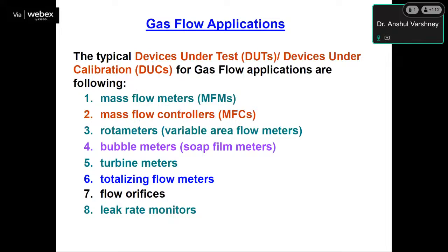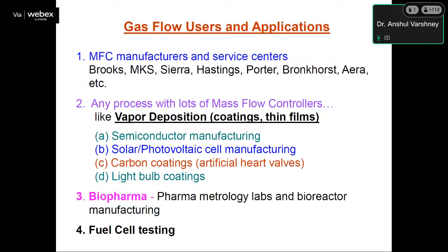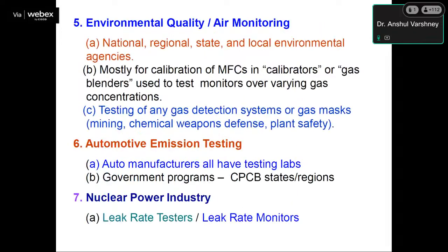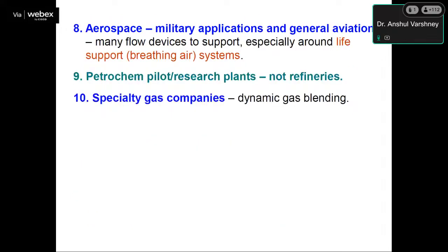So basically, gas flow applications. The typical devices under test for gas flow systems are mass flow meters, mass flow controllers, rotameters, bubble meters, turbine meters, totalized flow meters, flow orifices, and leak rate monitors. We provide service to mass flow meter manufacturers and their service centers like Brooks, MKS, Sierra, Hastings, and so on. Applications include any process with lots of mass flow meters, biopharma industries, fuel cell testing, environment and quality monitoring, automotive emission testing, the nuclear power industry, aerospace, petrochemical and research plants, and specialty gas companies.